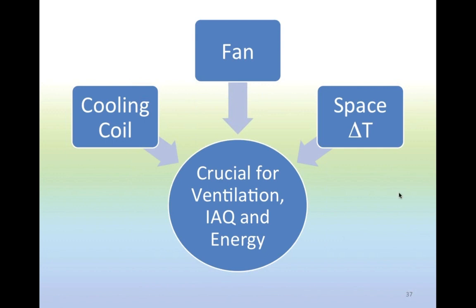The second strategy I would like to discuss here, well, it's not quite a specific technology-related strategy, it's a concept. From a design consideration and concept, how do you want to go about it? The issues that I'm trying to address here are space temperature difference, cooling coil and fan energy, and related IAQ issues. So from the point of view of ventilation, IAQ, and energy, the coil performance, no doubt we've seen the relevance and the importance of it, the fan energy, and the space delta T. Now, the space delta T is the temperature difference between the room condition, say 24 degrees Celsius, and the supply air temperature. It's not the off-coil condition, but the supply air temperature. That's the space delta T we're talking about.